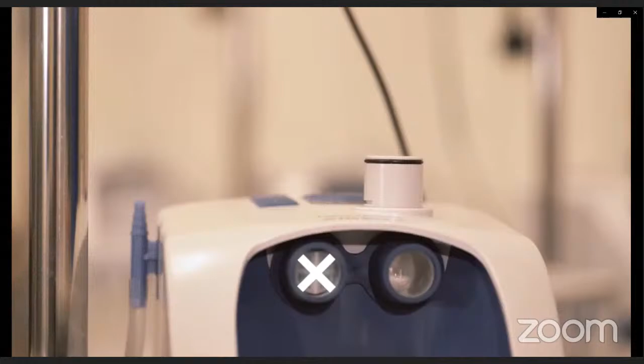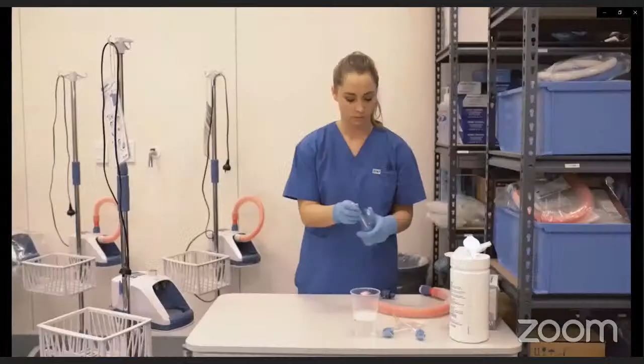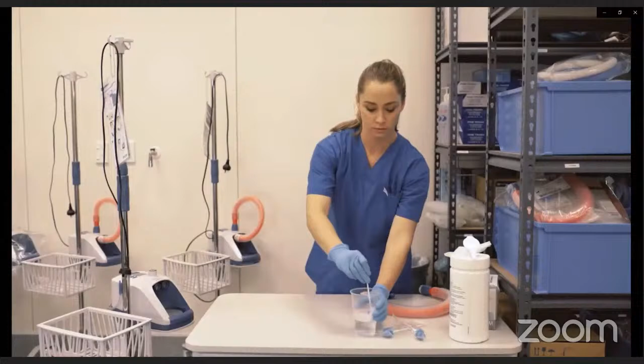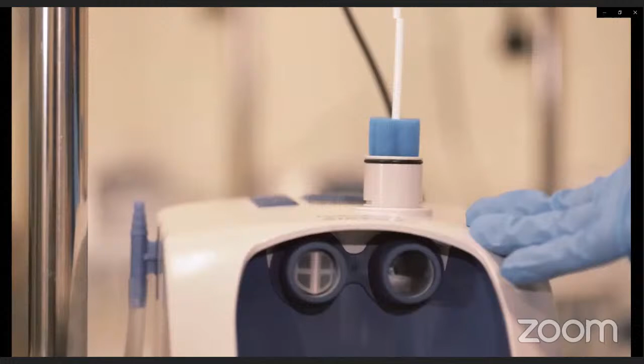The most important part to clean is the outlet elbow between the right chamber port and breathing tube port. Do not clean the left-hand chamber port, as this can damage the non-return valve located at this port. First, dip the cleaning sponge stick in a solution of warm water and mild detergent. Thoroughly clean the outlet elbow from both ends as far as possible, continuously rotating the sponge stick.